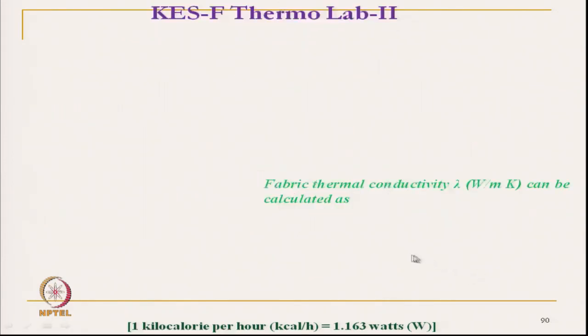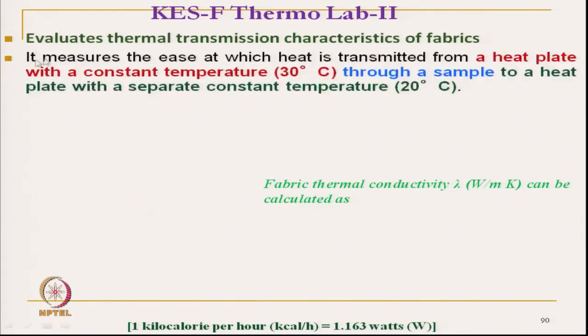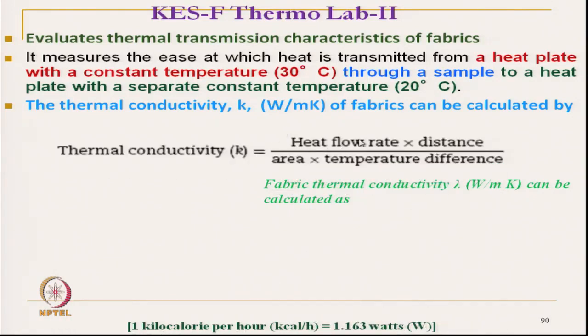Another method for measurement of thermal transmission characteristics is the Kawabata method, KES-F Thermo Labo. It evaluates the thermal transmittance characteristics of fabric where two plates are used. In between the two plates, the fabric sample is sandwiched. A hot plate with a constant temperature of 30 degree Celsius and a cold plate with a lower temperature of 20 degree Celsius are used, and the amount of heat flow is measured. The thermal conductivity is measured in terms of heat flow rate and distance, divided by area and temperature difference.